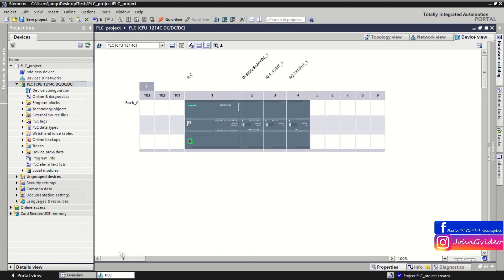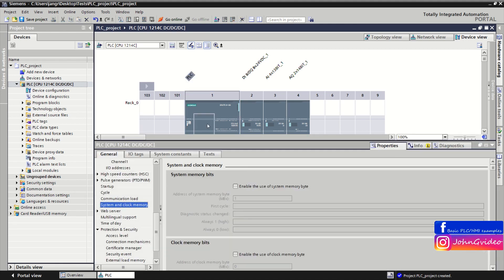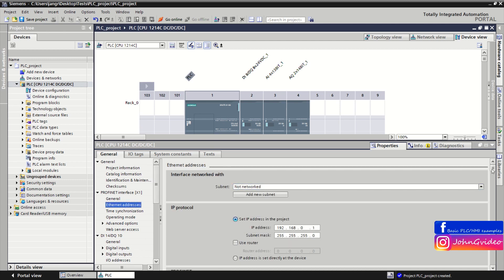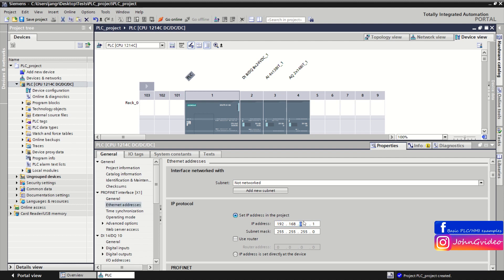Now we have the complete PLC rack for our PLC project. Click on the CPU in your PLC rack to open its properties. It is necessary to define the Ethernet address of your CPU — for example, use a specific IP address, insert the subnet mask, and if you use a router, also insert the router's IP address.